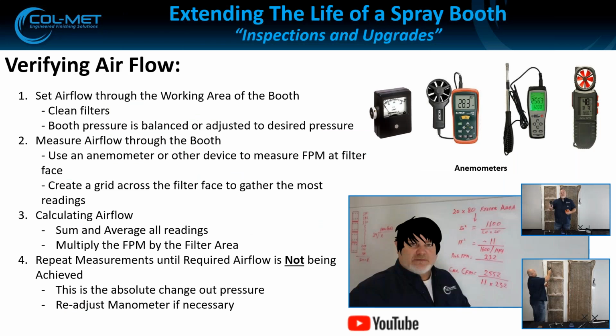If you're looking at the airflow in the booth, I talked about that. We have a YouTube video, and I've talked about it in depth through a webinar as well. What I'm saying is we want to measure the airflow in the booth when it's clean, and make sure the booth is balanced to however it's supposed to perform. You can use an anemometer, hot wire, some type of velometer, whatever you have handy. Just make sure it is rated for the range of velocity we're looking to see, which is somewhere between, say, 100 and 300 or 400, maybe 500 feet per minute.